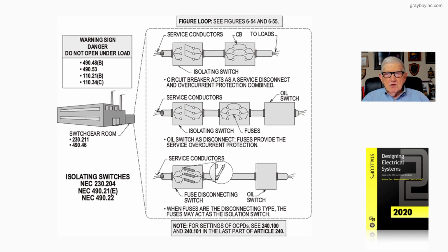And then in the last illustration, we show a disconnecting means and a fuse switch being used as disconnecting means. And notice fuses rated for the purpose could be used there. But you see that the service conductors is using a fusible disconnect properly rated to disconnect the oil switch. So when fuses are the disconnecting type, the fuse may act as an isolation switch. Overcurrent protection for these systems are found in 240.100 and 240.101 in the NEC.